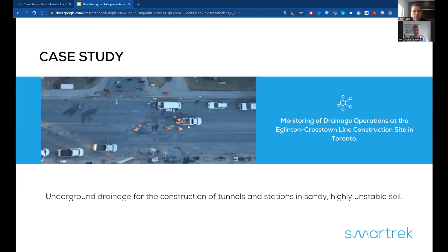So what we did was install monitoring vacuum sensors on the pumping line to make sure the vacuum was always present and that the vacuum distribution was also good on the line. We also installed current sensors placed at each electrical panel to make sure the amps being pulled from those panels were always within normal parameters.